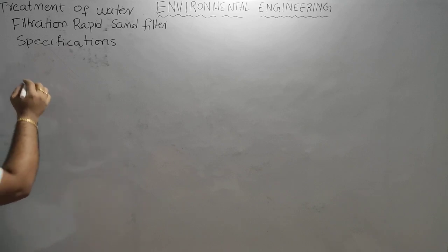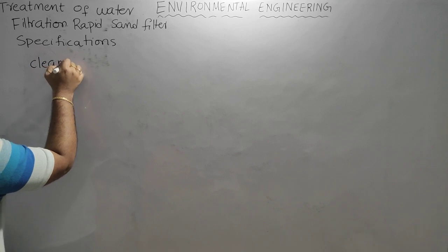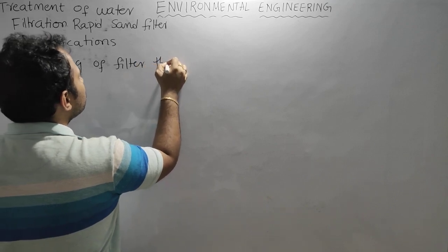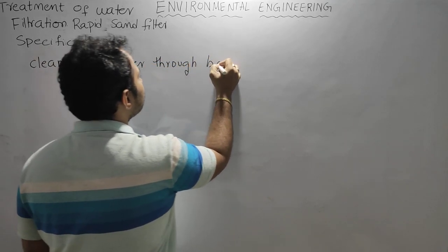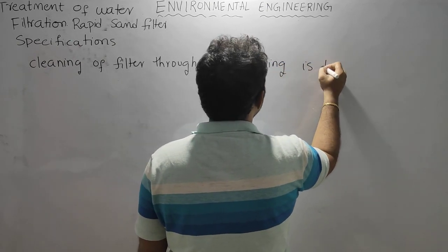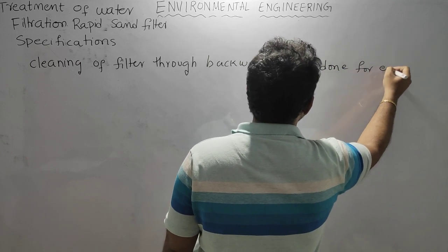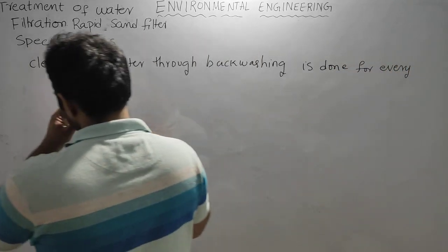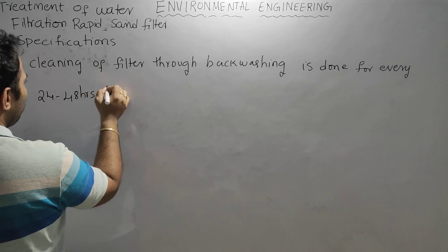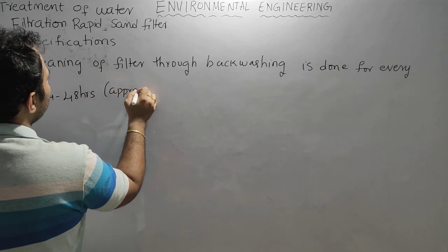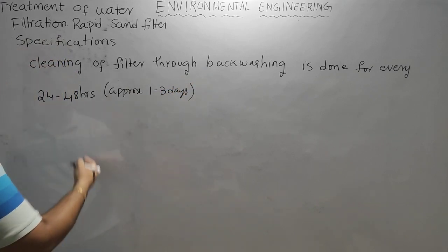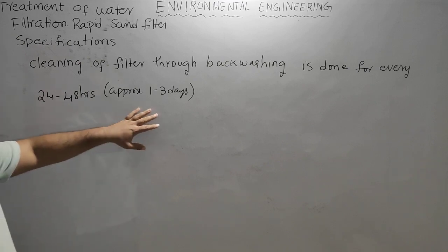So backwashing, cleaning of the filter through backwashing, is done for every 24 to 48 hours, or approximately 1 to 3 days. It is not that you were told it is 1 to 3 days; I am writing it as 24 to 48 hours. So these are approximate limits.